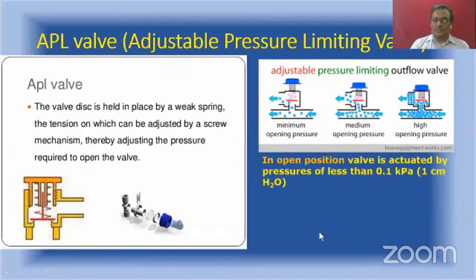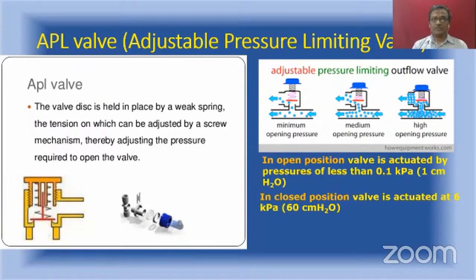Two points which are of importance are, in the open position, the valve will be opened by a pressure of around 1 centimeter of water. That means that much resistance will be offered to the patient's expiration. Okay, mild. But when the valve is fully closed, totally closed position, still the disc can be opened at a high pressure of 60 centimeters of water. This is actually a safety measure.